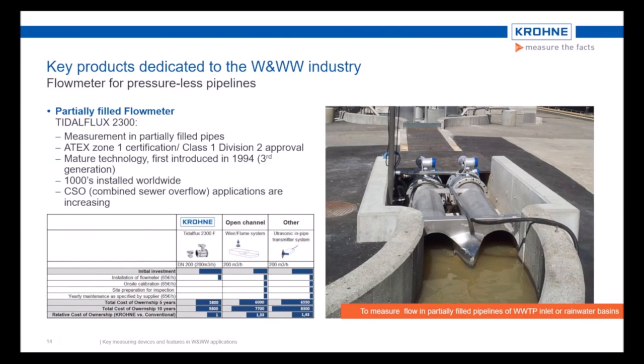Next key product is a special flow meter for pressureless pipelines, which can be partially filled. Mostly used in wastewater networks, sewage treatment plant inlets, or rainwater or stormwater pipe networks. So this mag meter is working like a conventional mag meter, but with an additional capacitive level measurement, which is integrated behind the coating and therefore without contact to the medium. So even when hydrogen sulfide occurs, this guarantees complete corrosive-free measuring when the level in the pipe is going up and down. This meter comes with an explosion certification class 1 division 2, which is required in the applications where that flow meter is used.